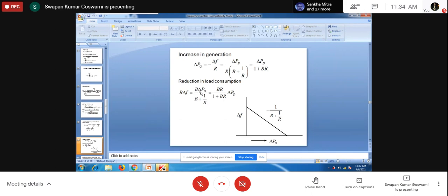Immediately after that, as I explained, the load will appear as an impedance to the system. As the impedance has been changed, what is happening? There is more current delivered. That means current will flow to that load. There will be more current delivered by the system to the output. So the output torque of the generator increases. The input torque remains the same. So there is some decelerating force acting on the generator.